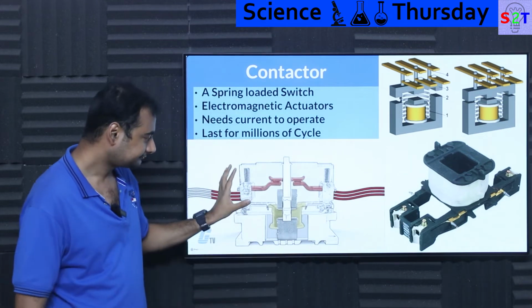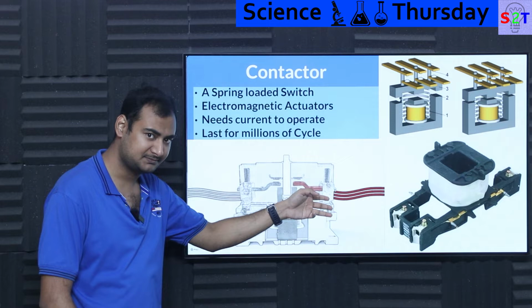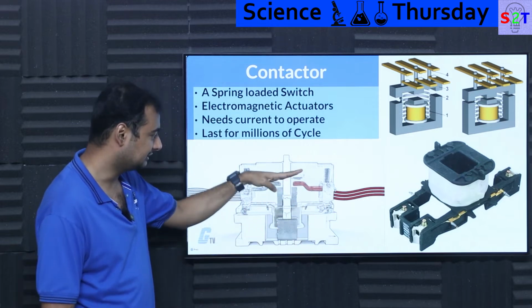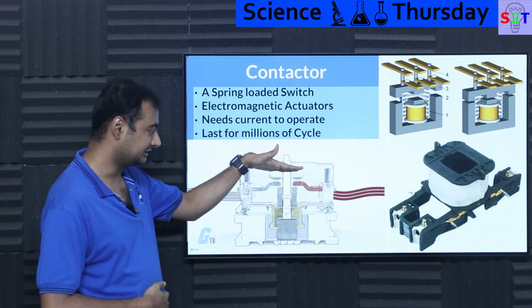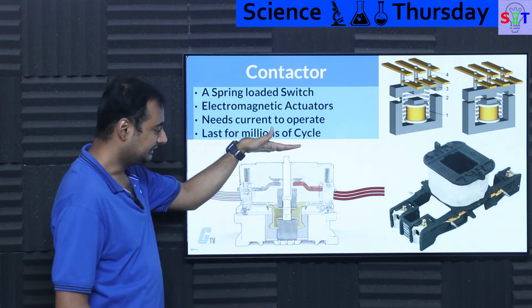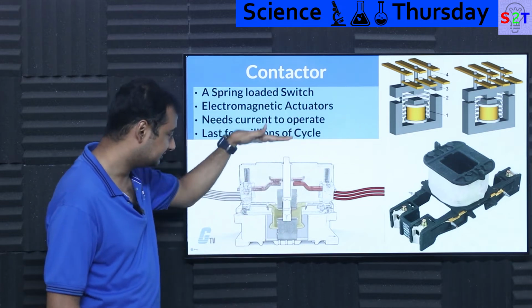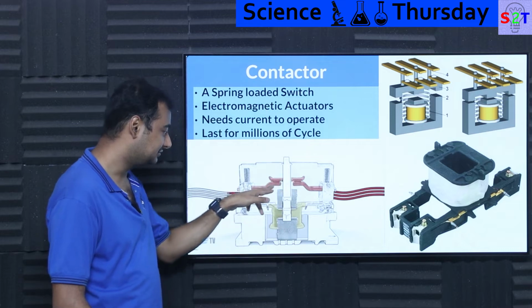And an electromagnetic actuator, basically a coil, is what actually turns it on. Most contactors are generally three-phase. The three-phase power comes in, and there is a floating bar that is supposed to connect it but does not, until the moment you turn on the coil. The coil creates a magnetic field that pulls this bar down, and then the plunger makes the contact.